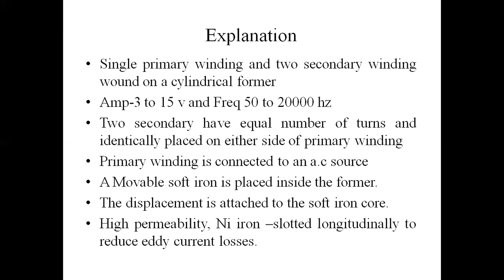In practice, the core is made of high permeability nickel iron, slotted longitudinally to reduce eddy current losses. The entire assembly is placed in a stainless steel housing to provide electrostatic and electromagnetic shielding.